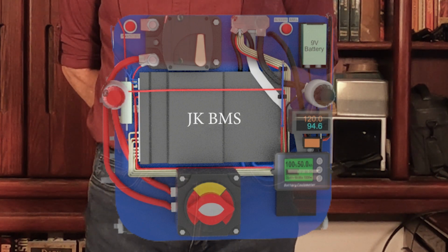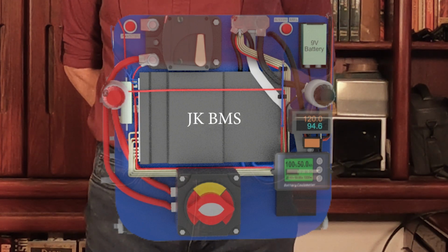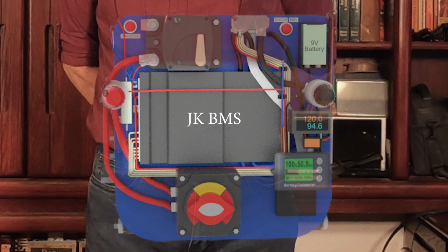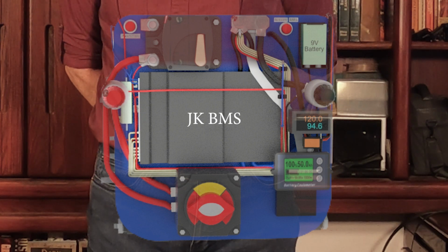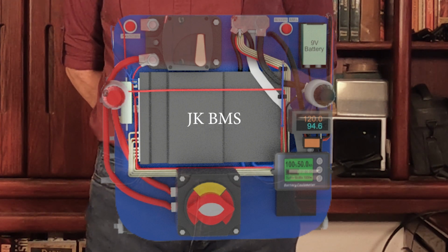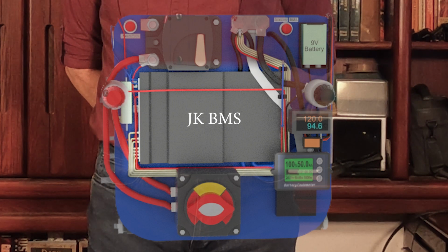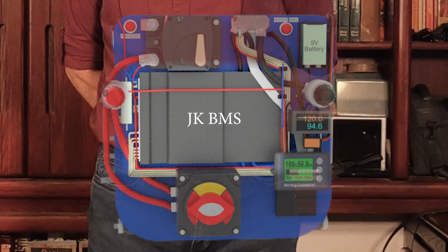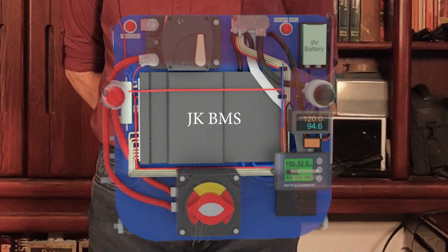This is the JKBMS, which has excellent reviews and a lot of excellent features. For example, it has low temperature cutoff, over and undercharge protection, high and low cutoff settings, maximum charge and discharge amount settings, Bluetooth connectivity to allow easy adjustment of the parameters without opening the case, and a 2 amp active balancing system, which uses capacitors to move energy from the highest charge cell to the lowest.